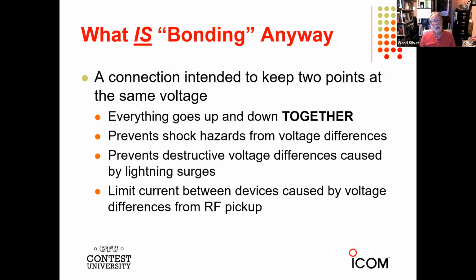And if you can prevent the current flow by limiting the voltage differences, you're miles ahead. So it accomplishes three things: prevents the shock hazard, prevents the destructive voltage differences during lightning transients, and it limits the current between devices in your station caused by RF pickup.